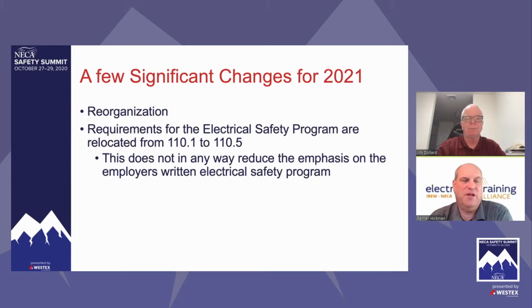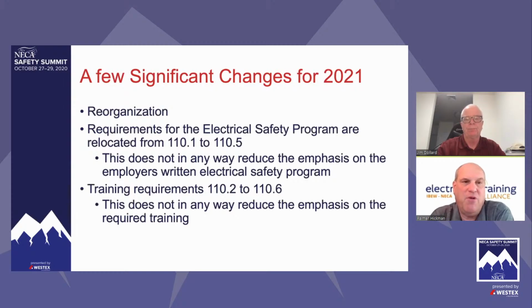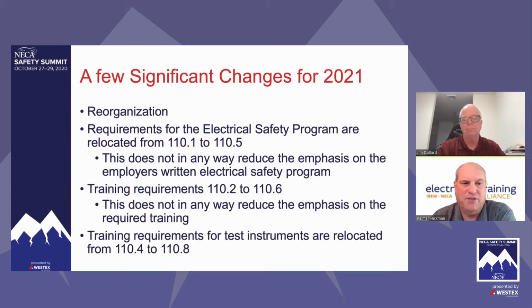And then another relocation is the next bullet point, the training requirements. So it used to be, you go into Article 110, the first thing you see is electrical safety program. The next thing you see is the training requirements. It moved from 110.2 to 110.6. And then the training requirements for test instruments are relocated from 110.4 to 110.8. That's where it says only qualified people can use test equipment.